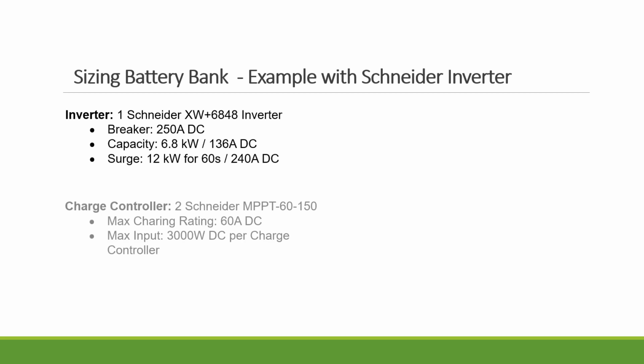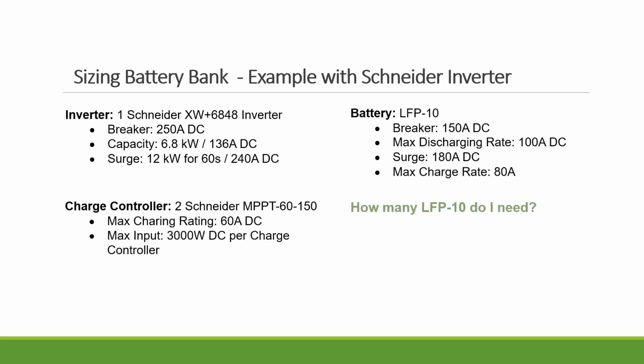Now we're going to decide how to select battery banks, and there are a few steps we have to go through. In this case, we select one XW6848 with two Schneider MPPT-60-150. The array size is around 6 kW. We're going to use the LFP-10, and what we're going to do now is determine how many LFP-10 you need based on the consumption, and also based on the inverter and charge controller that we selected.